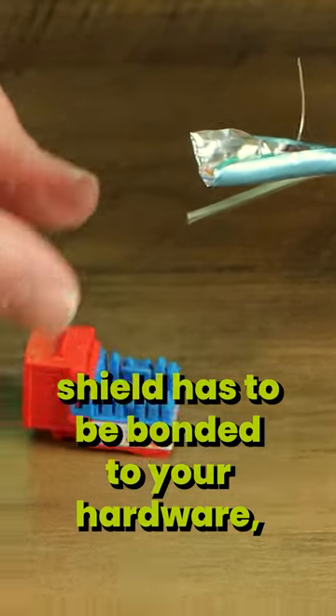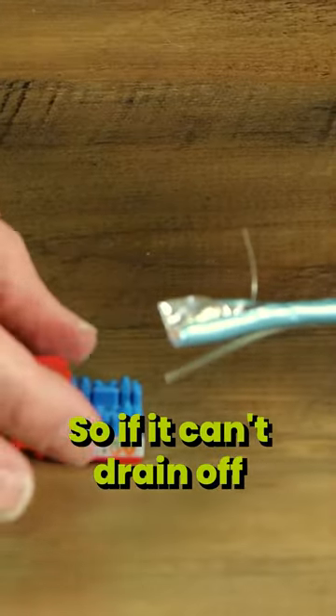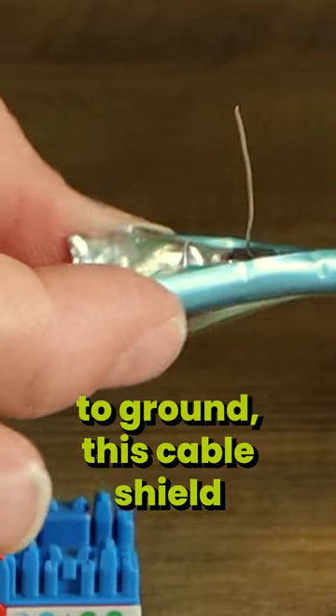The cable shield has to be bonded to your hardware so it can drain off to ground. So if it can't drain off to ground, this cable shield will not function properly.